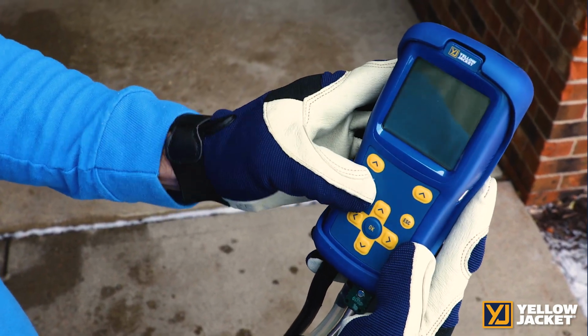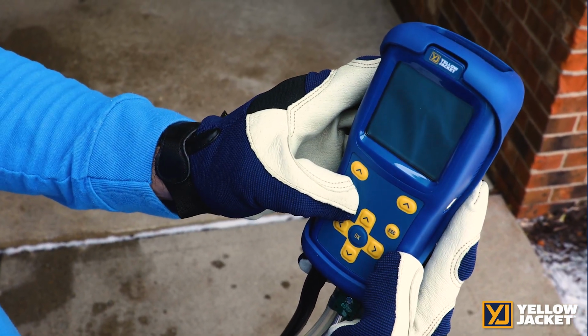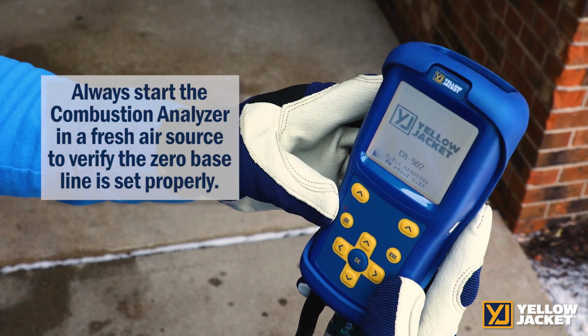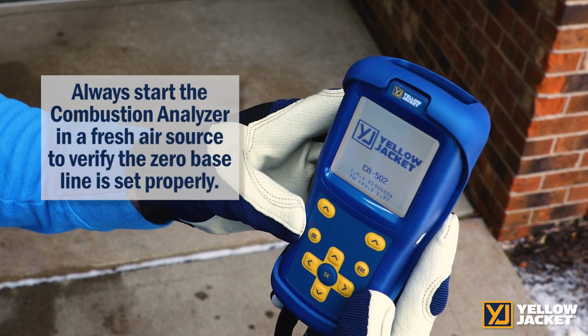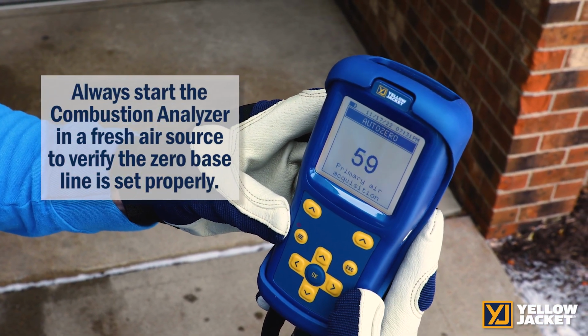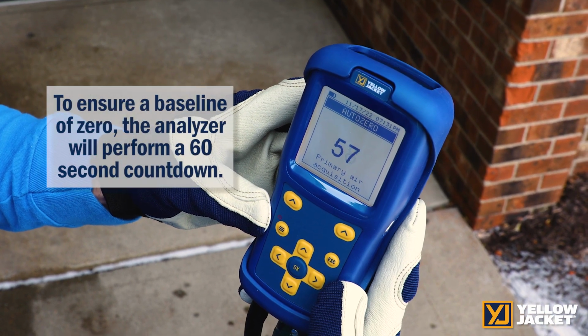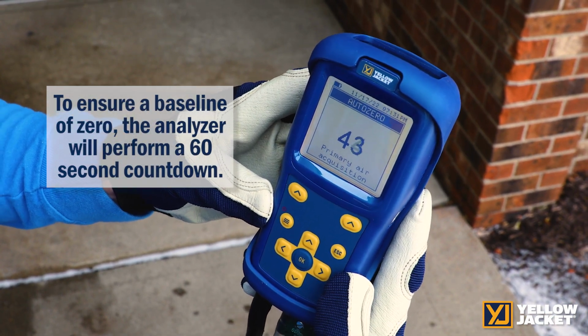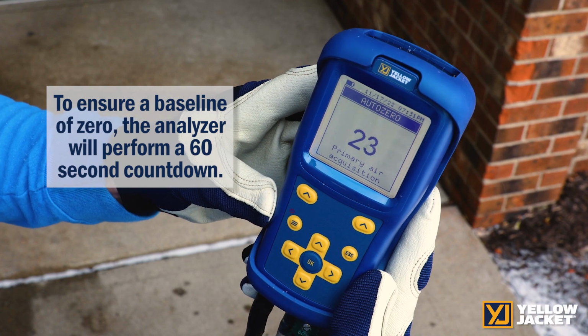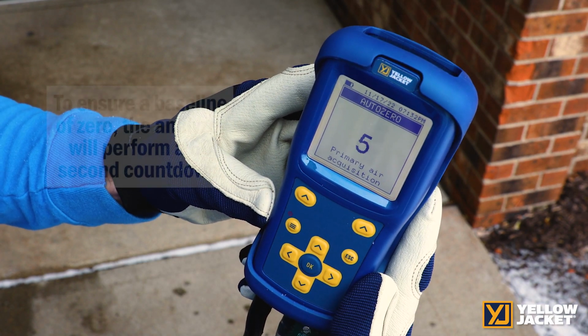Then, outside in clean fresh air, we will turn the CA502 on. We are doing this in an open air source to ensure that our zero baseline for the CO is an actual zero. If you do this near a CO source, your baseline will be higher and will appear that your overall CO levels are lower than they actually are.